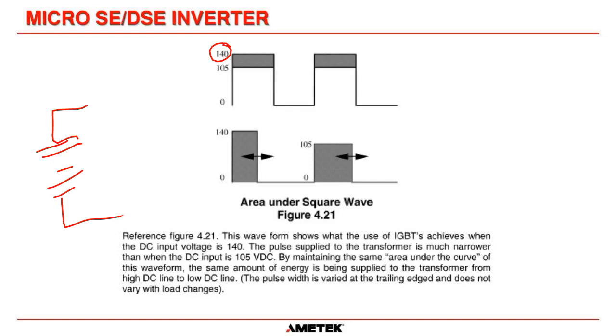And then on the lower end, we have 105 volts, and that is the end of discharge voltage that most battery manufacturers recommend. It's actually 1.75 volts per cell, and if you multiply that by 60 cells, it comes out at 105. So our inverter is designed so we can have a range of 105 to 140 volts going into our inverter bridge.